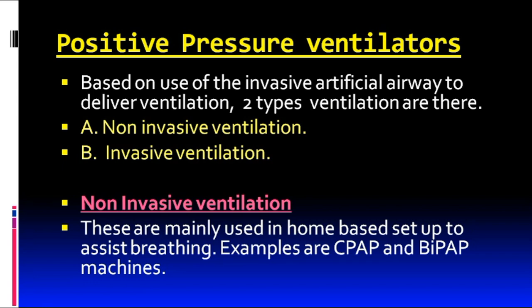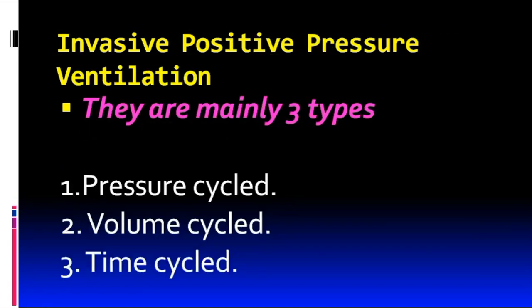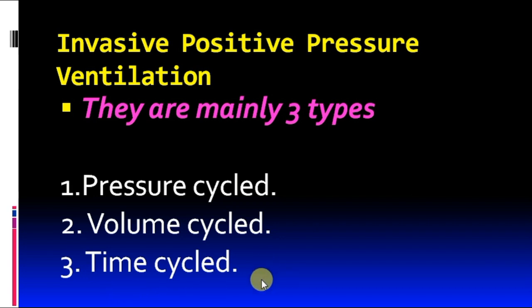Invasive positive pressure ventilators are further classified into three types: pressure-cycled ventilators, volume-cycled ventilators, and time-cycled ventilators. Time-cycled ventilators are used only in neonates, so we will mainly discuss pressure-cycled and volume-cycled ventilators.